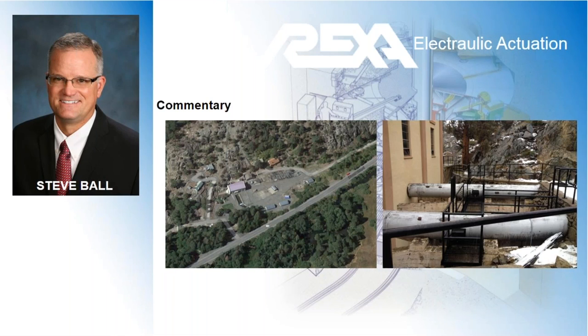And there was an oiled dash pot on the end of that linkage that would have a slow rate of closure, which would take something of about 45 to 50 seconds to complete a full closure of that water. So it was a way to protect the penstock system. The problem that we had encountered historically at that plant is that it would go off grid, or the grid connection to the transmission system would be frequently interrupted through the winter months, sometimes in other months as well, either wind or some other issue. But that plant would not be able to accept load or reject load quickly enough to the satisfaction of carrying islanded load. So it was always set up to just trip on loss of system.